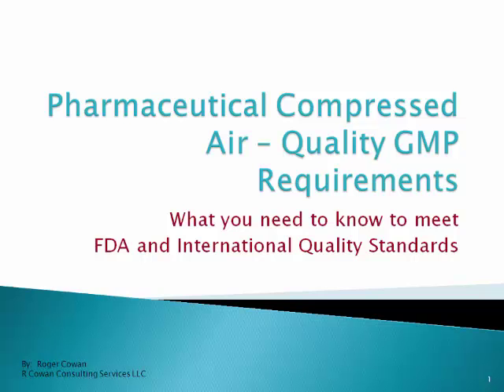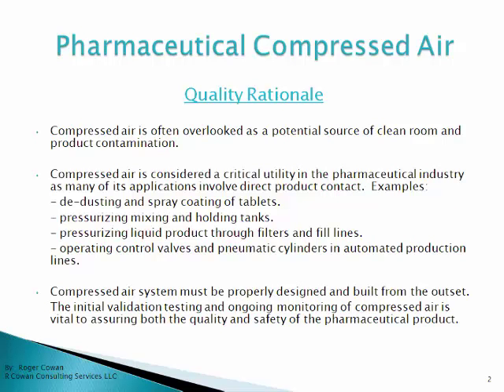Let's talk about the quality rationale around compressed air. Compressed air is often overlooked as a potential source of contamination. It's used for spray coating of tablets, pressurizing various tanks, pressurizing liquid product through filters, fill lines, and also operating control valves and pneumatic cylinders on automated production lines. These are a few examples of direct product contact with compressed air, so the compressed air system must be properly designed and built from the very beginning. It's also important to do a thorough job on validation testing and monitoring of the compressed air.